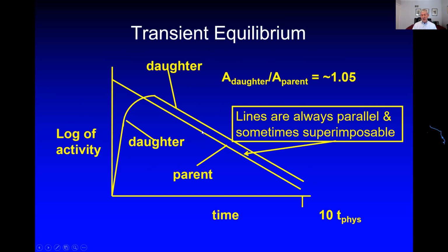Remember, technetium can't decay until it's formed. It's being formed with a 67-hour half-life. So the technetium in the equilibrium mixture is going to look like it has a 67-hour half-life. We know it doesn't, but in that mixture, it does. Now, technetium's curve looks like this, except for one thing. This line here is actually below the molybdenum line down here. It's very unusual for this activity to exceed the parent. It can do so by about maybe 5%, but we don't see it very often. And in technetium, we don't see it. It just comes down parallel, right down here. Okay.